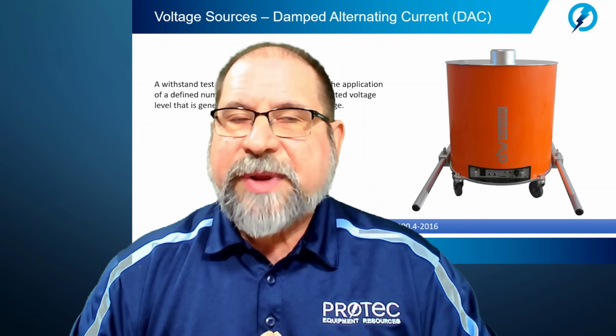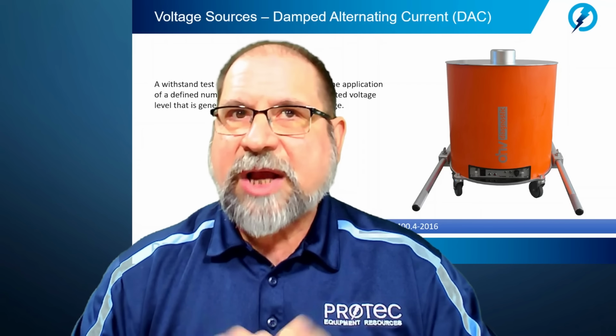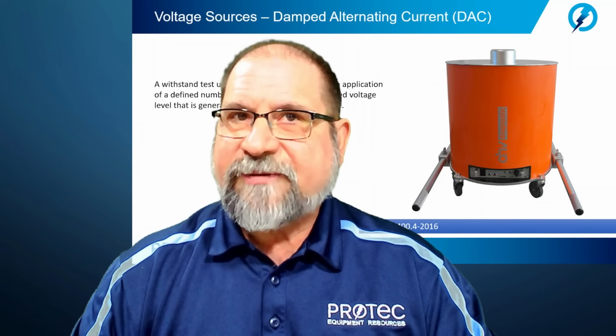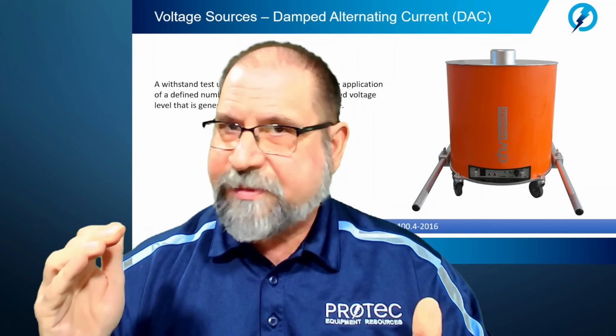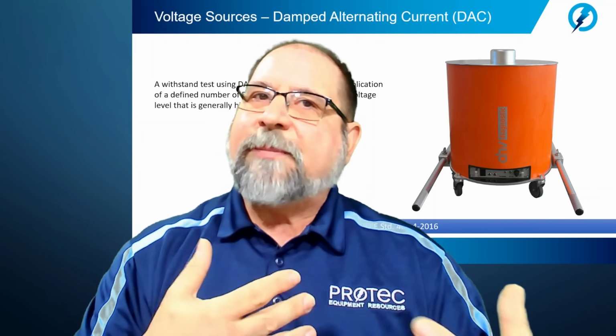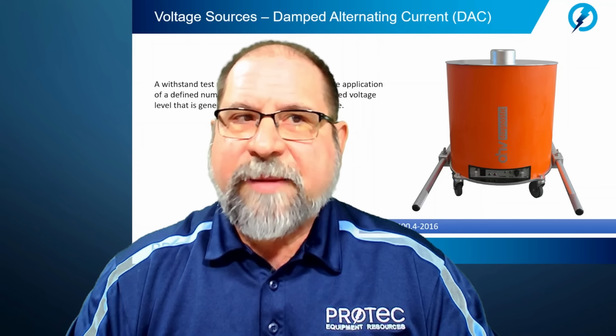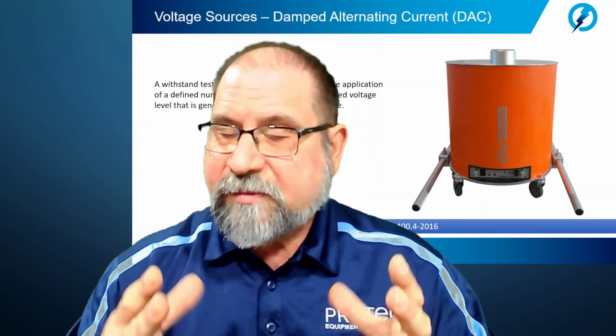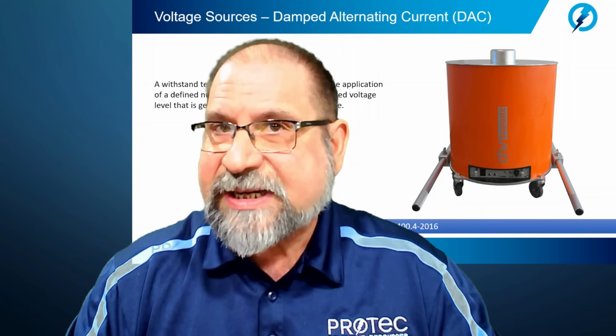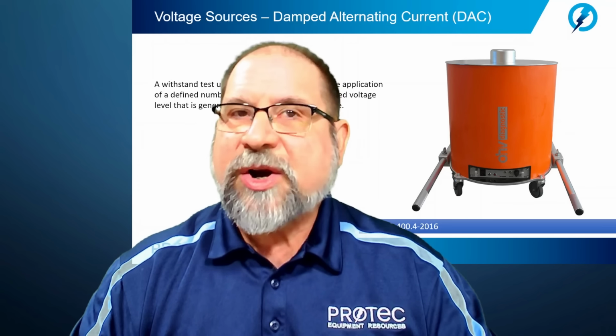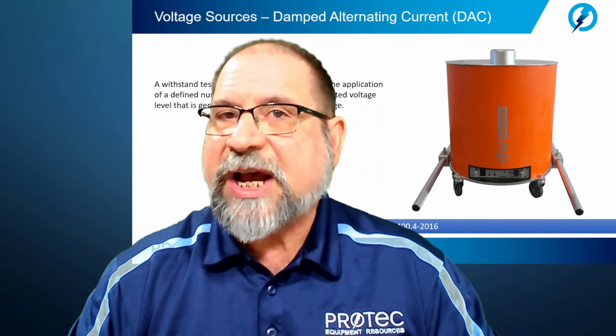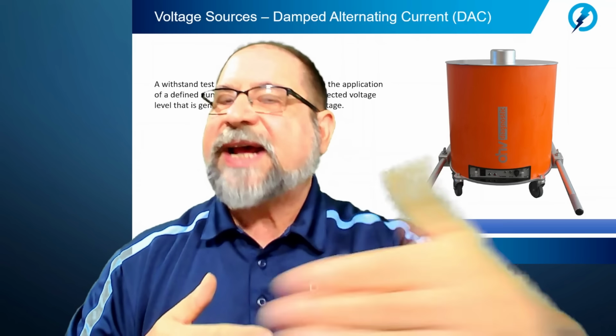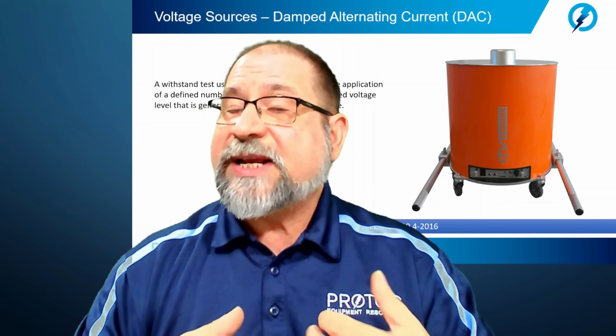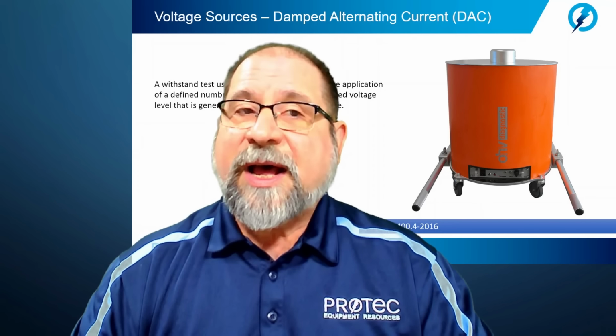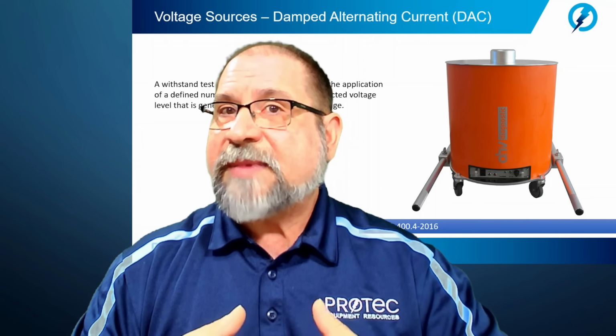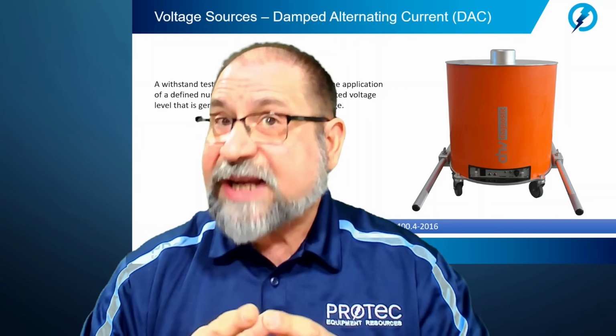In my personal opinion, when we look at the DAC technology, at the medium voltage levels up through and including maybe 69 kV, I believe we do see a more viable solution in the VLF testing. Testing at the 0.1 hertz sinusoidal or even the cosine rectangular. It is a continuous output, stressing the insulation uniformly as opposed to the excitation or pulsing type tests.